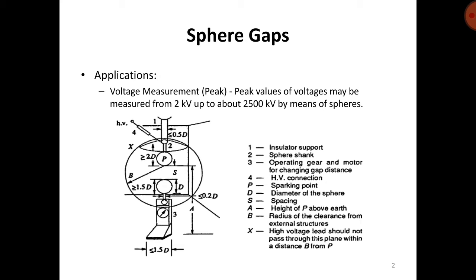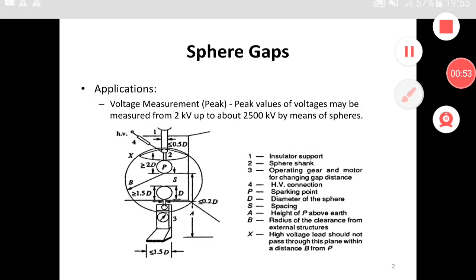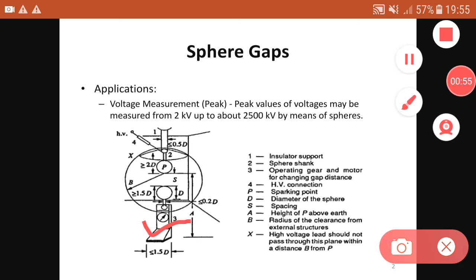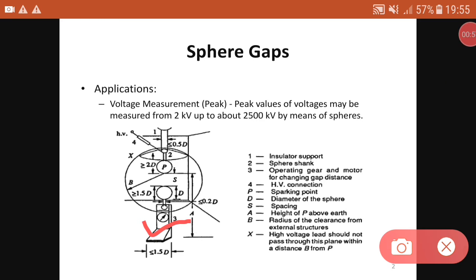So here labels are given. First one is the insulator support, 2 is the sphere shank, third one is the operating gear and motor for changing gap distance. Here we can see the operating gear and motor for changing gap distance. 4 is the HV connection. Here we can see the HV connection, which is given to the upper sphere.